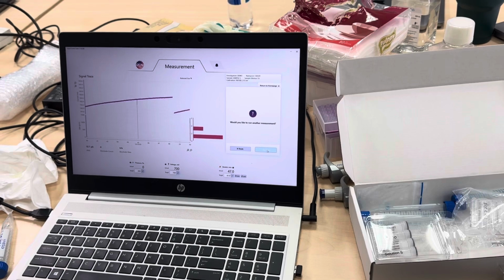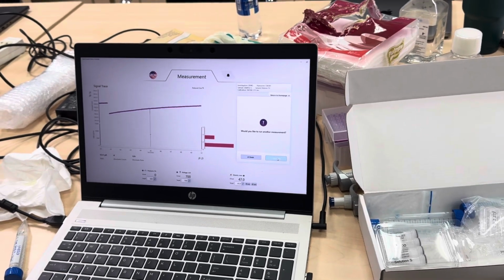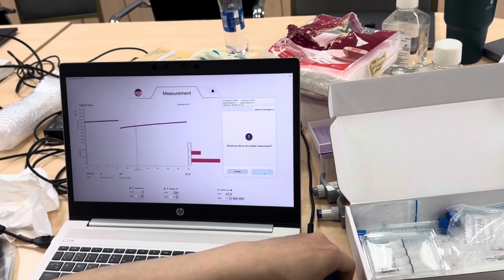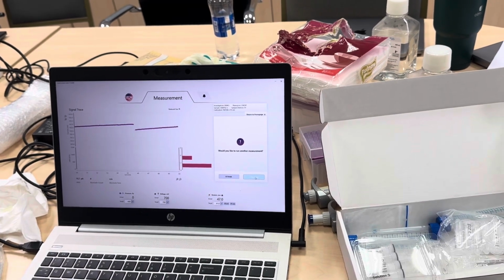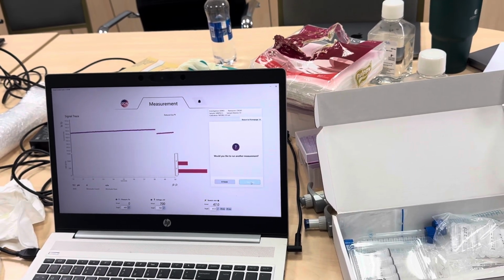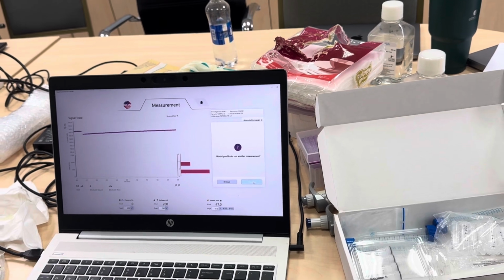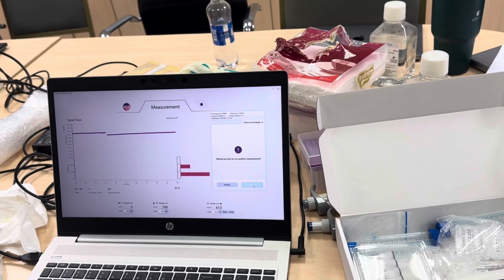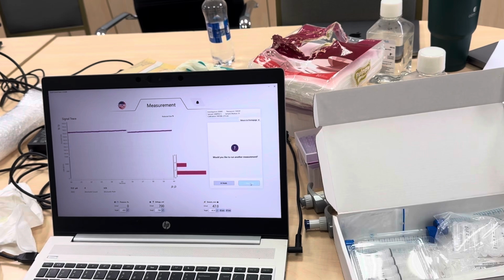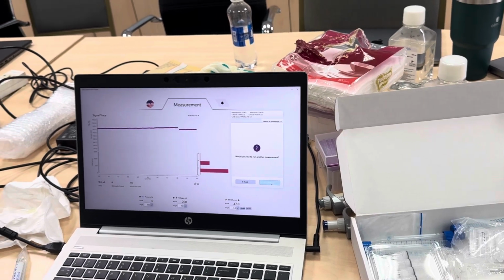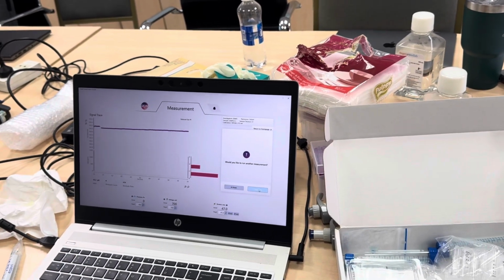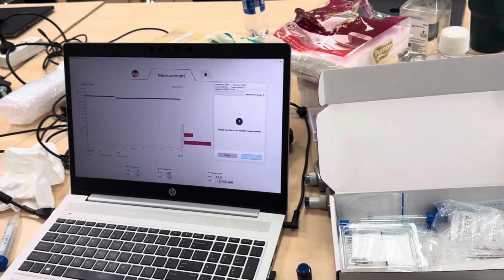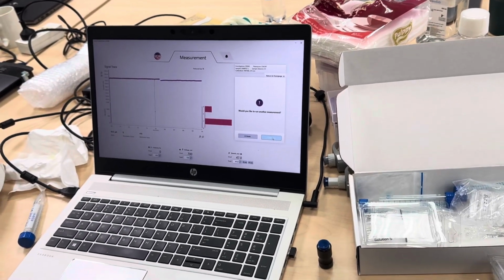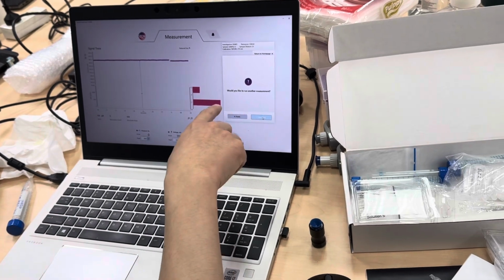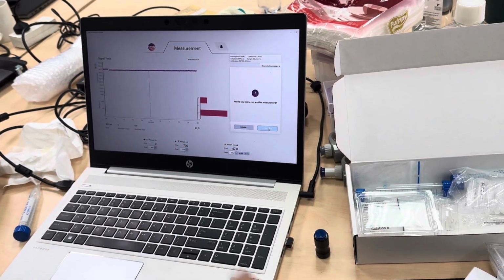So basically you can see the speed is quite fast. Calibration will be done every time I use any EV or exosome sample. Usually we suggest calibrating every 3 to 4 samples. After 3 to 4 samples, you see that it asks whether you need another calibration. You click yes. We need to do another calibration and then run the other samples.